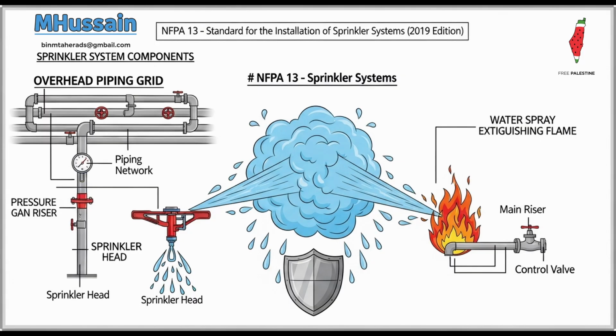Antifreeze actually changes the fluid dynamics, specifically the viscosity and the surface tension of the water. That change can interfere with the ESFR head's ability to generate the required high-momentum spray pattern needed for true suppression. Even a slight change in those fluid characteristics can compromise the entire system's performance, which is exactly why that listing requirement is so strict. Right.